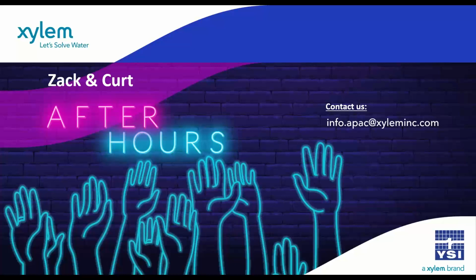You've got to just keep in mind, it's probably a good thing that I'm not in sales, and it's not a good thing that Zack, the product manager, is on here with us, because I can tell you a whole bunch of reasons why I don't like YSI electrodes, but they're a necessary evil. And the reason I say that is they're temperamental. They're not as accurate as most other sensors. They take more calibration.